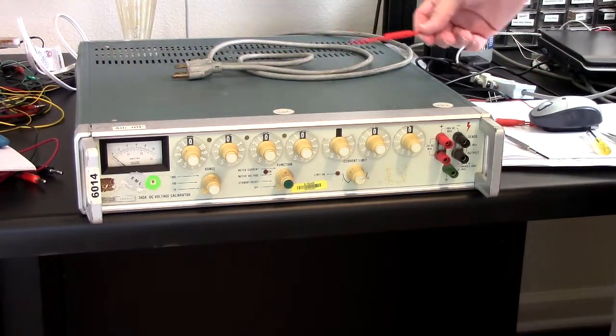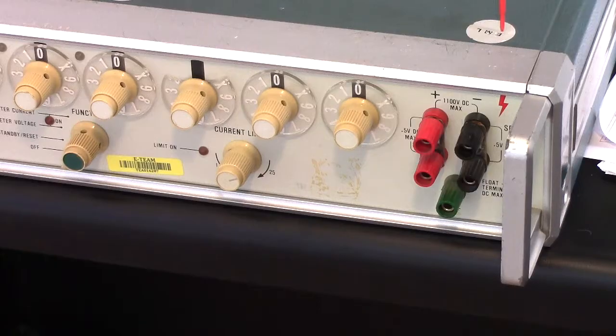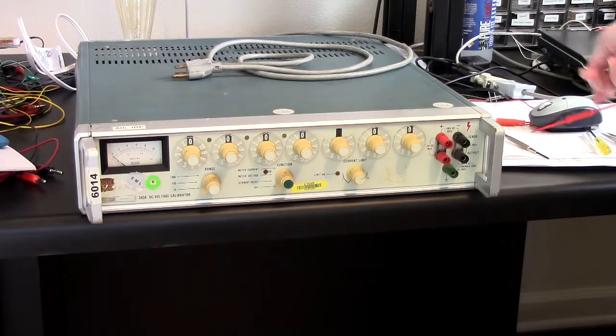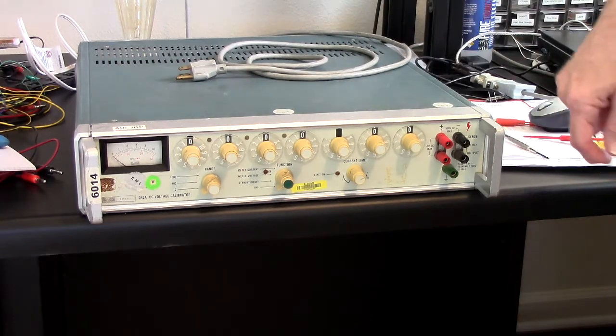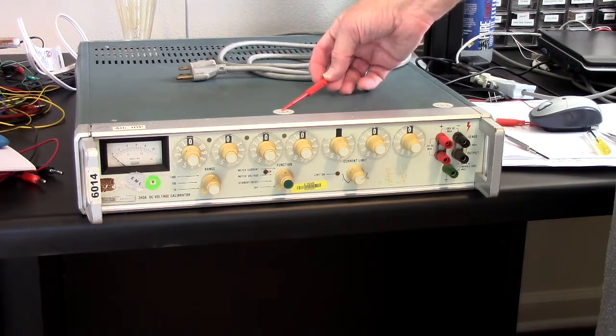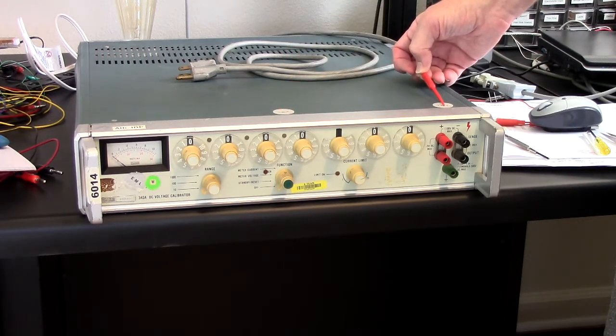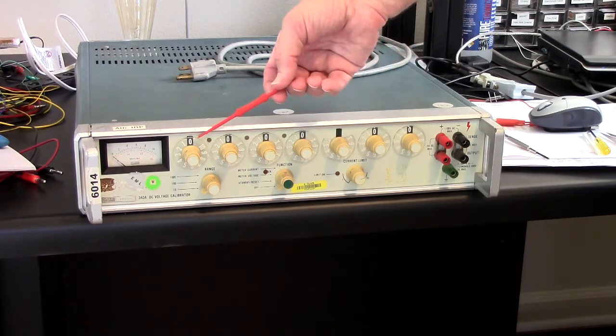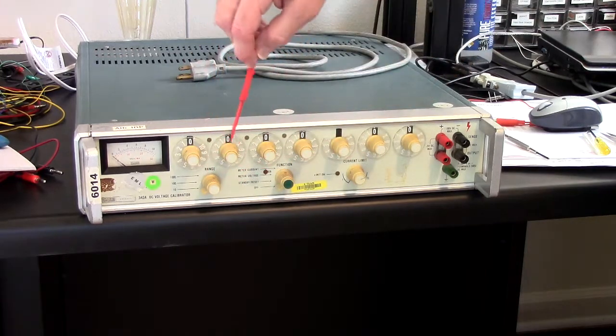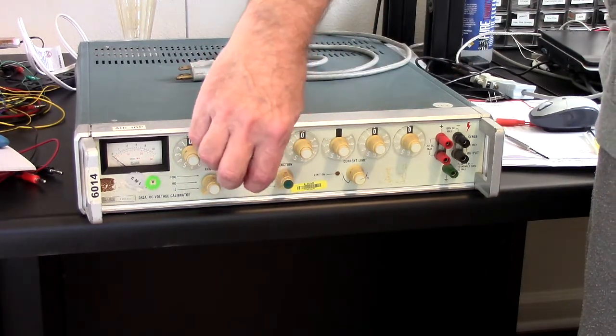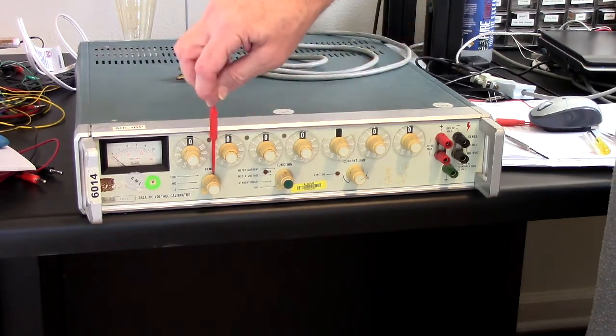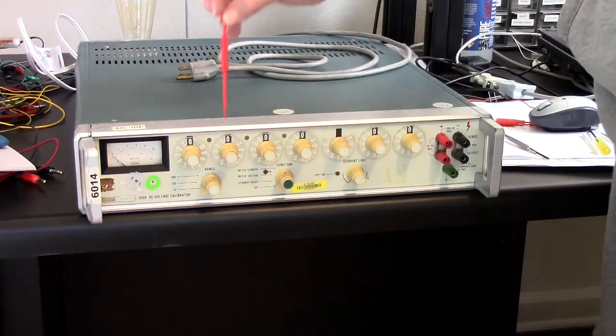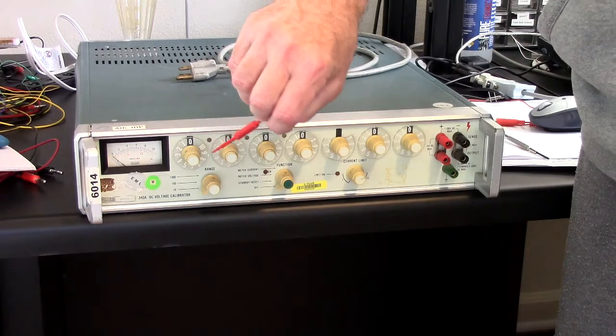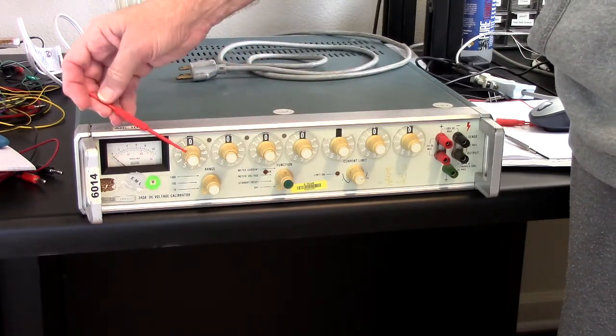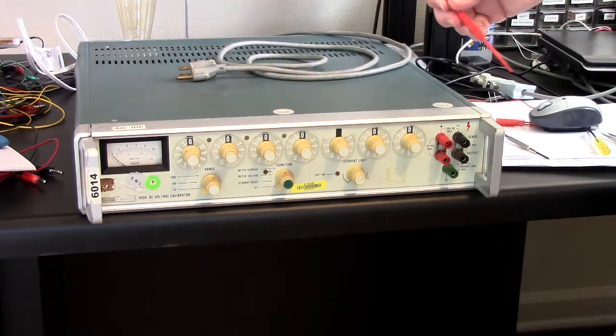Looking back now, there are 6 screws on the top cover. 2 of them still have stickers on them, so this thing has not been opened since it was last calibrated, which is a good sign. The other thing is there is something rattling around inside, which we'll find out. But no one has messed with the calibration. I also see that this dial is sticking out a bit, as is this one. The others are pretty much flush against the front of the panel, and there's a gap on these, which I don't understand. This one wiggles a little bit, and I can see the bushing in there that ought to be back. But those look like they'll come off, and I can readjust that.